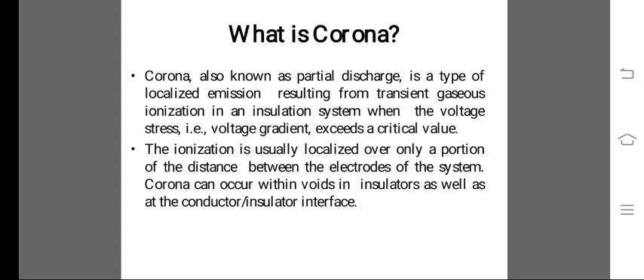What is Corona? Corona, also known as partial discharge, is a type of localized emission resulting from transient gaseous ionization in an insulation system when the voltage stress, i.e., voltage gradient, exceeds a critical value. The ionization is usually localized over only a portion of the distance between the electrodes of the system. Corona can occur within voids in insulators as well as the conductor or insulator interface.